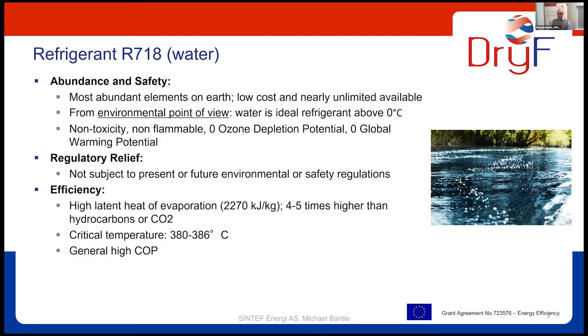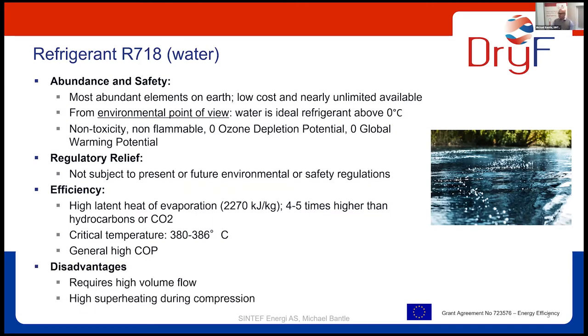It's also a very efficient working fluid, with a very high latent heat of evaporation. It's 4 to 5 times higher than that of hydrocarbons, or for example CO2, which are also common refrigerants in this area. The critical temperature is far beyond our working area here, so that's good. And when we make a general comparison of the efficiency, the COP of heat pump systems using water compared to other working media, we see we always achieve a somewhat higher COP, and that's because of the thermal properties. But no advantages without disadvantages.